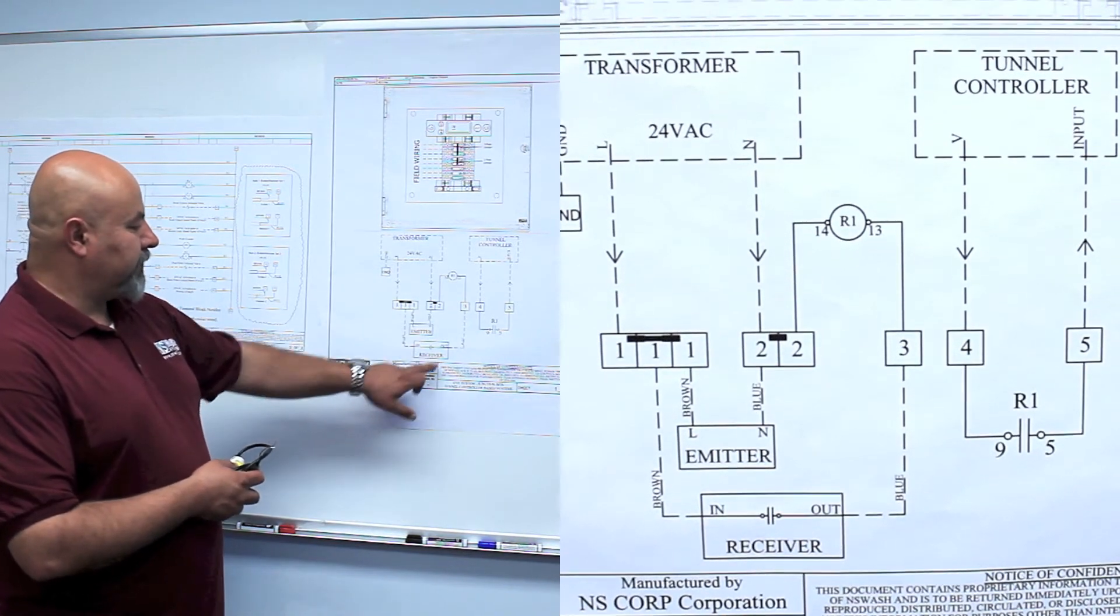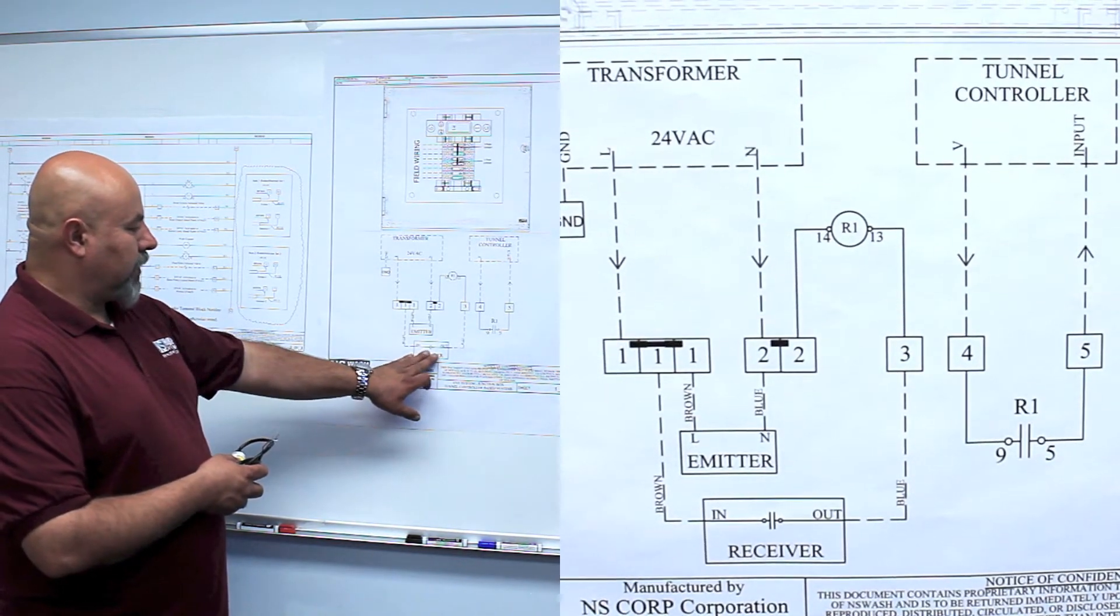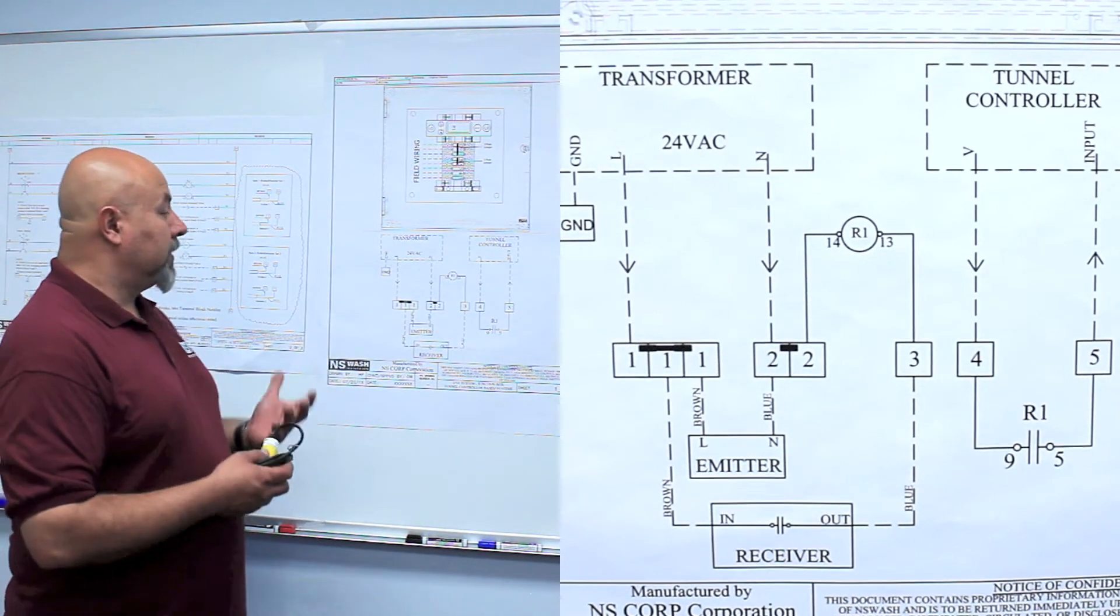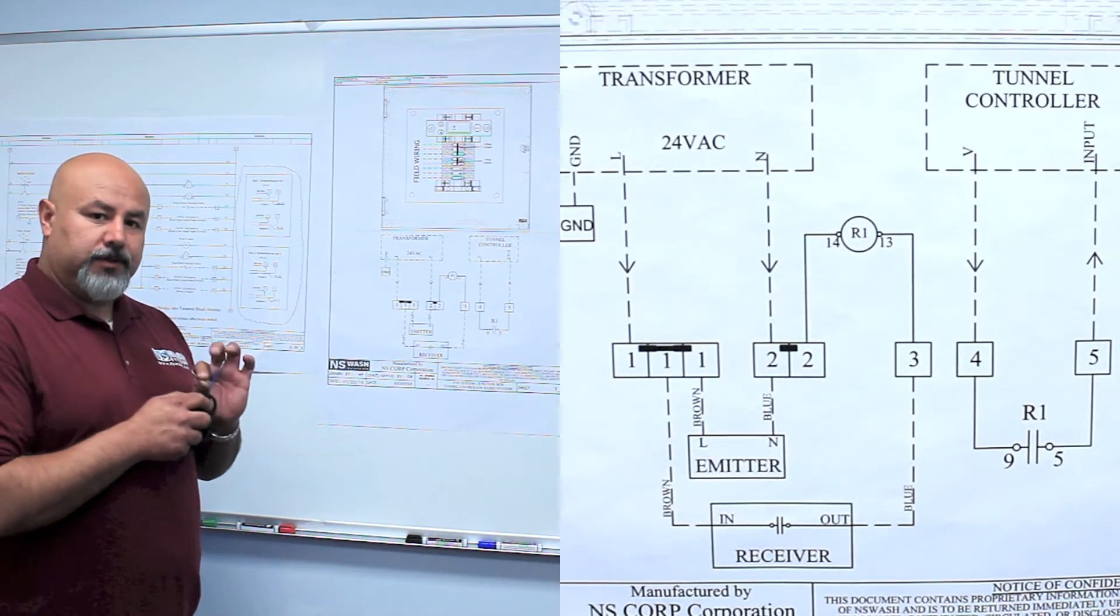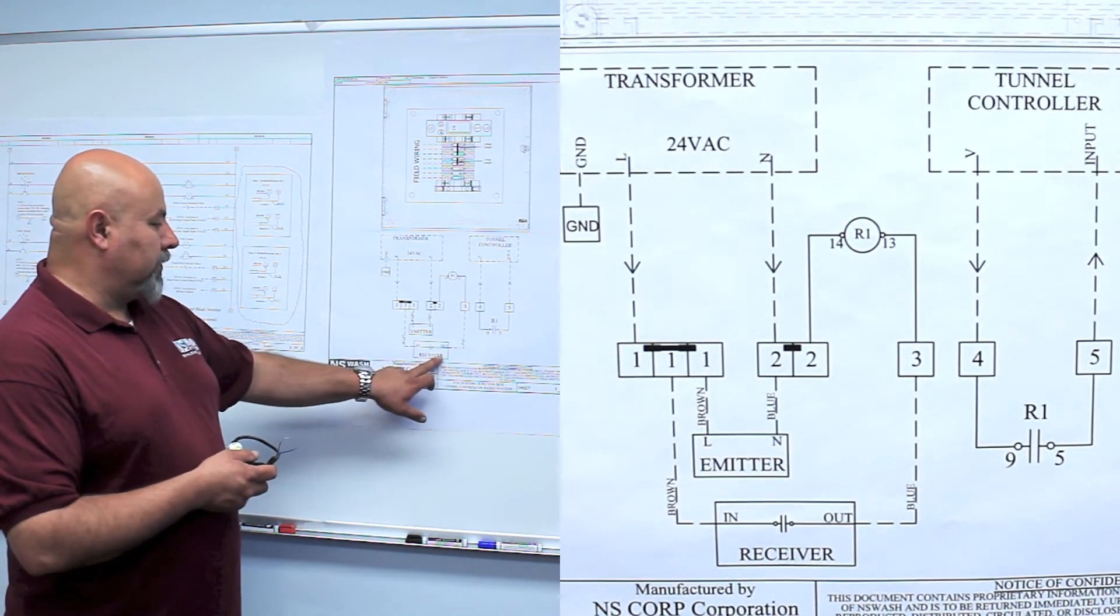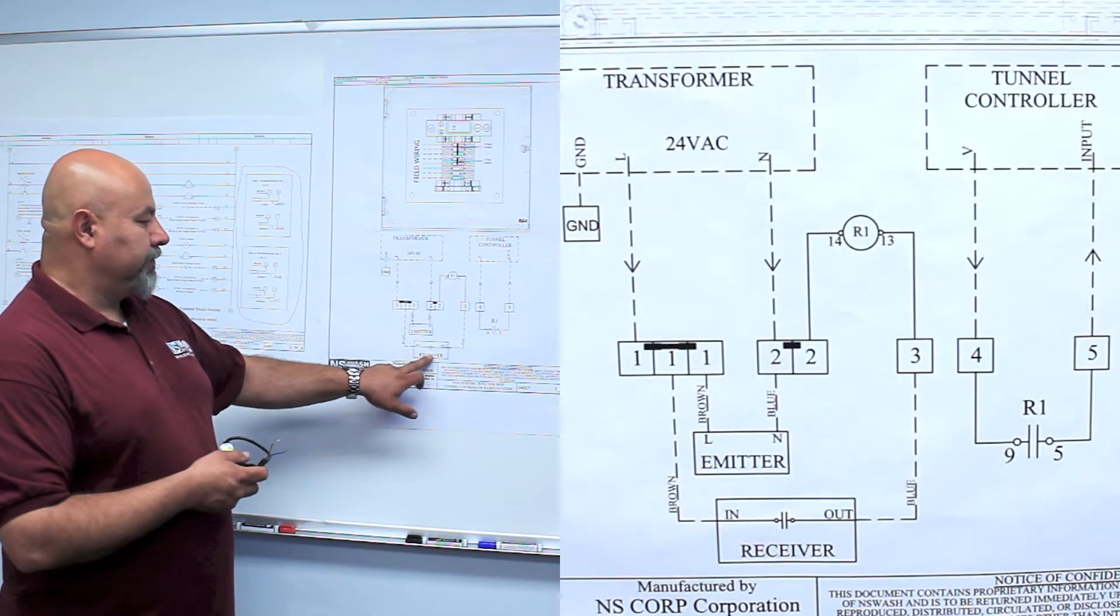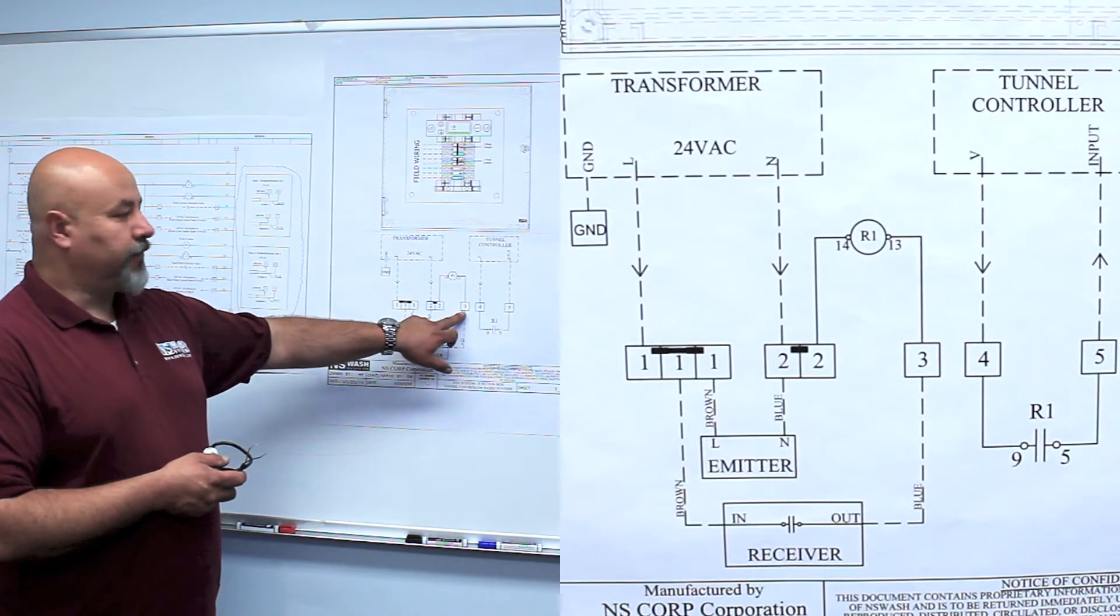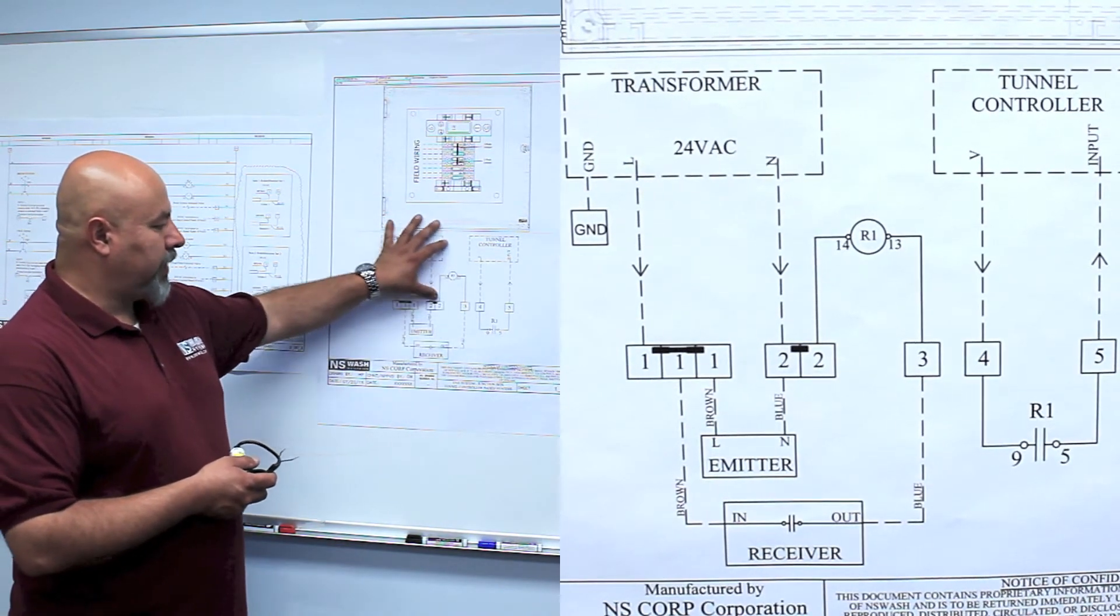The receiver photo eye, the brown wire goes to terminal number one. Again, that's the load because all the brown wires are always to load, the hot side. The other side of the receiver photo eye is the blue wire. The blue wire is going to terminal number three. This is a very simple little panel.